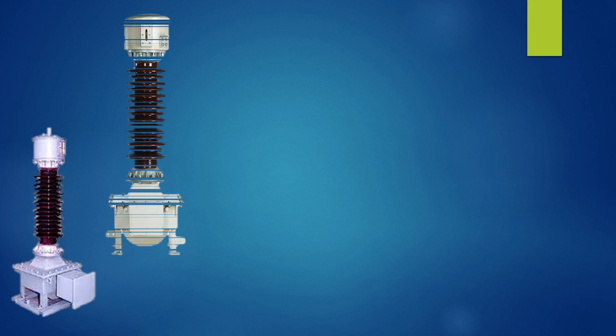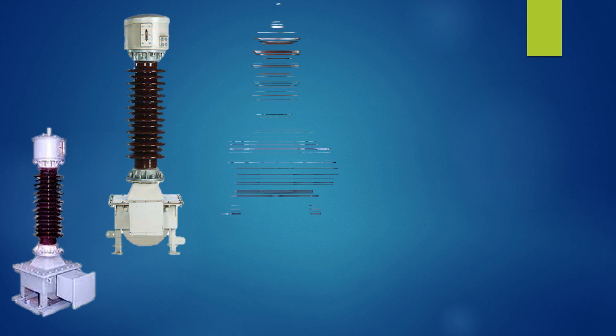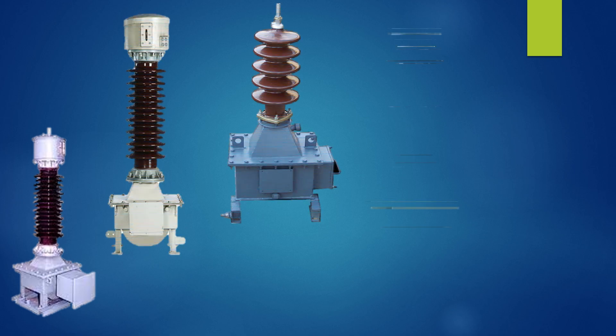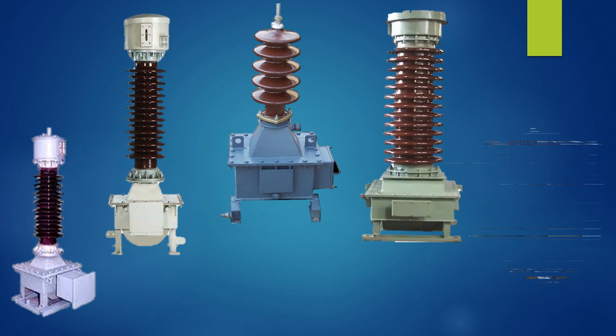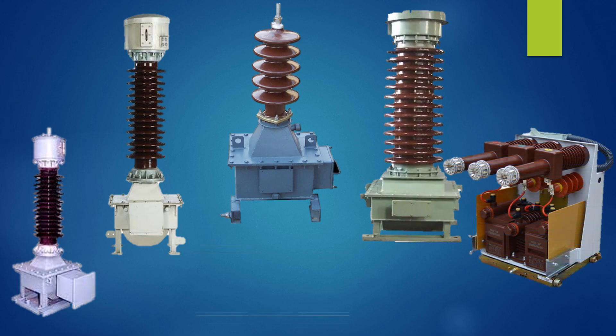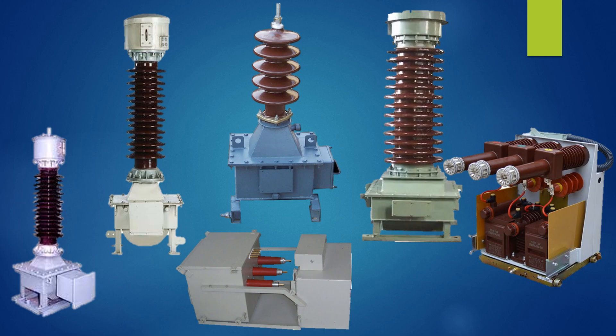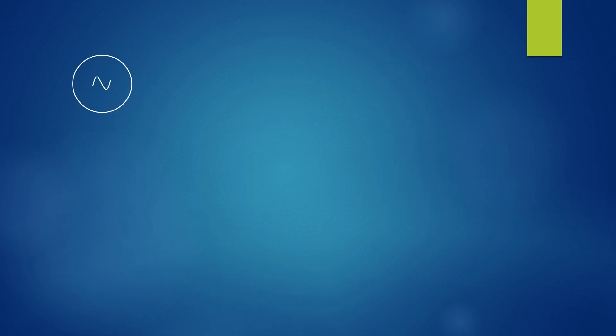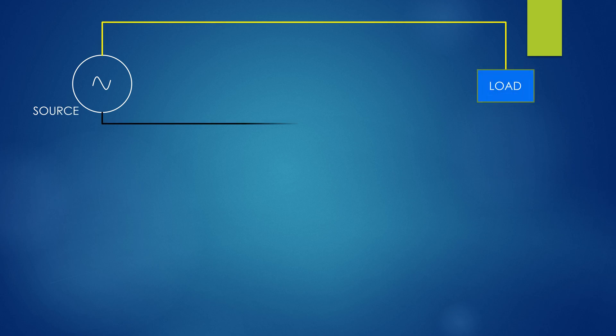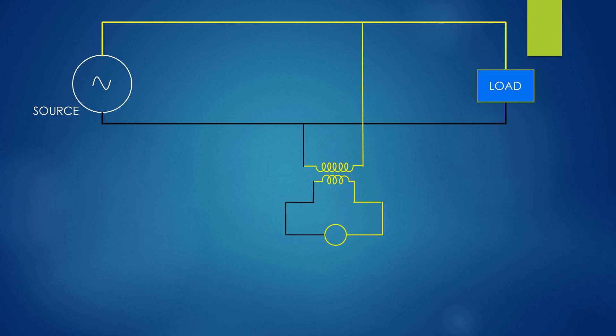According to the class of voltage and installation structure or place, different types of PTs are manufactured. In all cases, PTs are designed to have their secondary voltage at 110 volt line voltage, whatever the primary voltage may be.